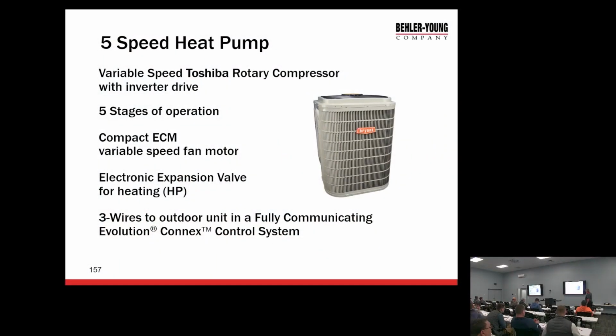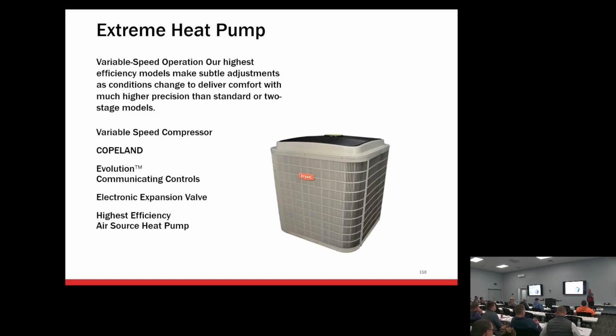Okay, the heat pump version of the same thing. Again, electronic expansion valve on the heating side. What do we have on the cooling side? It's a TXV, right? It's still a coil. You have a V coil, an N coil with the TXV on the inside. Okay, the extreme, this is the full variable. That's the great big doghouse sitting over there.